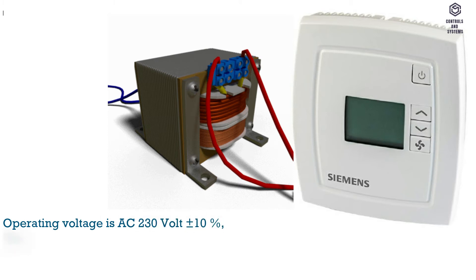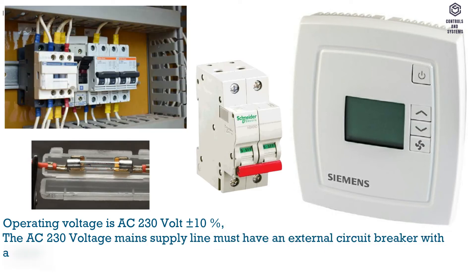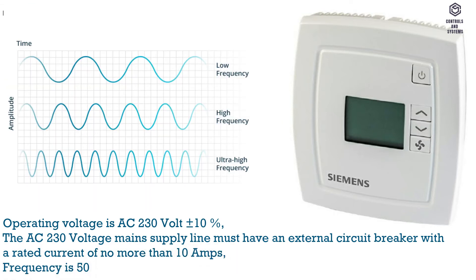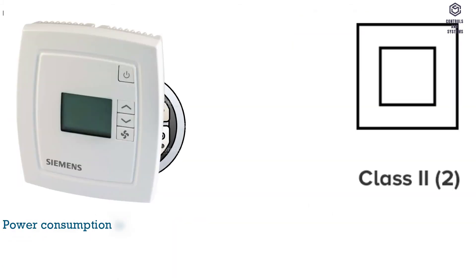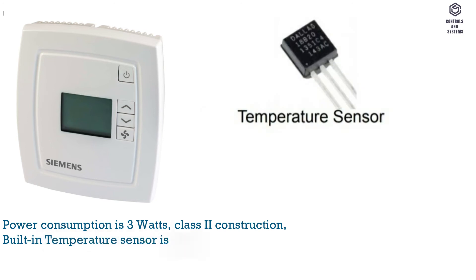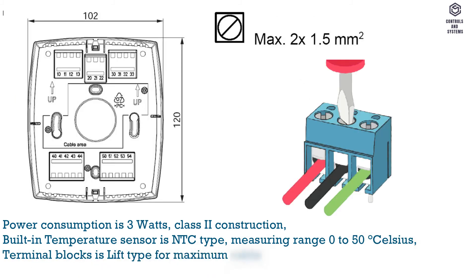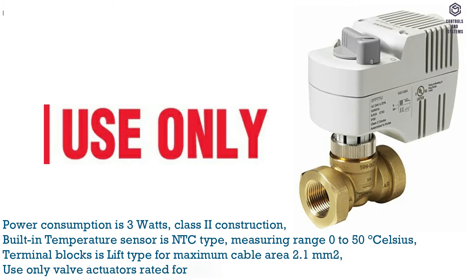Technical data — operating voltage: AC 230 V ±10%. The AC 230 V main supply line must have an external circuit breaker with a rated current of no more than 10 amps. Frequency is 50 or 60 Hz. Power consumption is 3 W, Class 2 construction. Built-in temperature sensor is NTC type, measuring range 0 to 50°C. Terminal blocks are lift type for maximum cable area 2.1 mm². Use only valve actuators rated for AC 230 V.